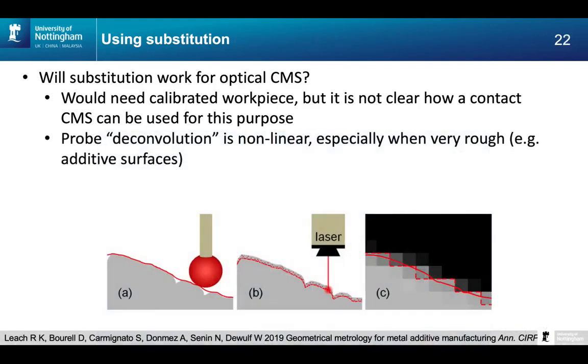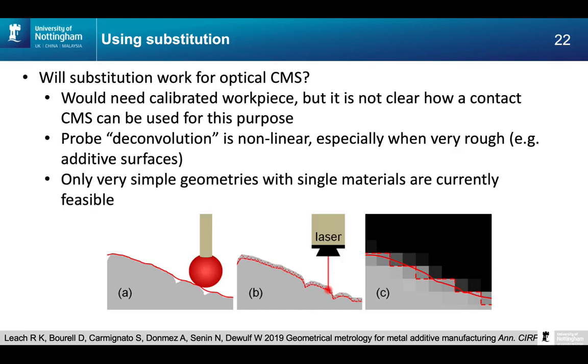The problem is when we're using optical systems, and there's an example in the middle there, and that's an X-ray system on the right, that we get a very different interaction with the surface due to the complexities we talked about earlier. So I put deconvolution in inverted commas there because deconvolution is a linear process and this is not a linear process. So extracting the effect of the probe in the case of an optical system is a very difficult thing to do. So it's not clear how we can use and calibrate the substitution method with optical systems. Probably only very simple geometries will apply, and if we've got complex objects like we showed with the additive surface, then we're going to have problems using this method.